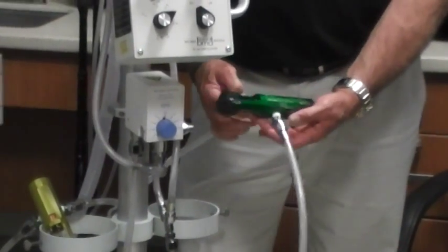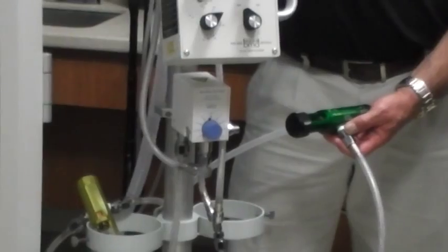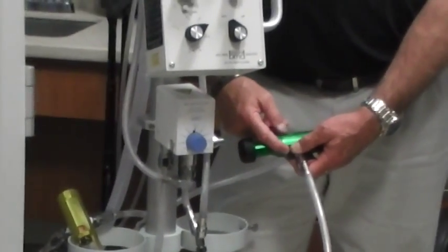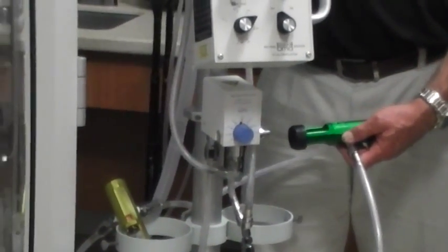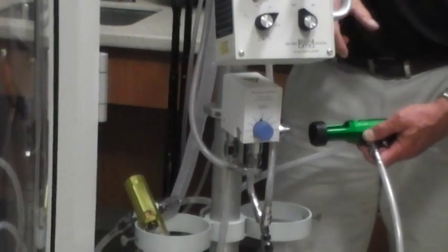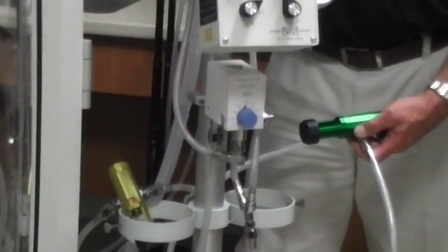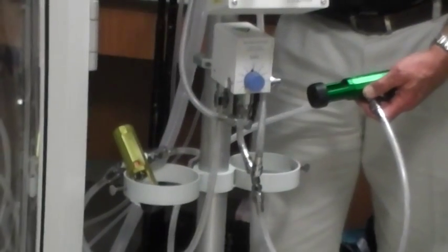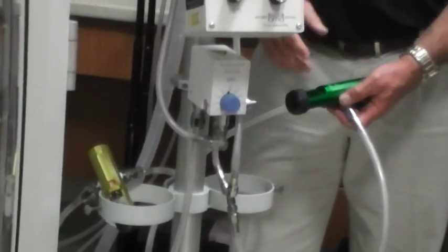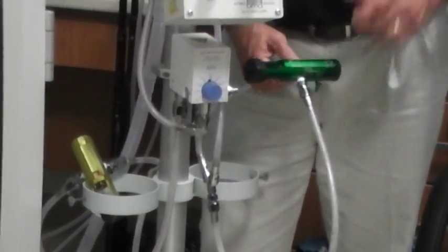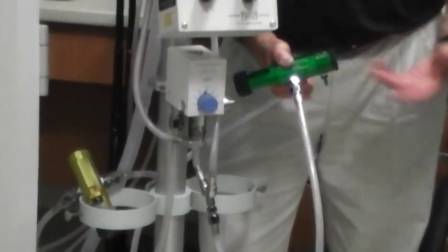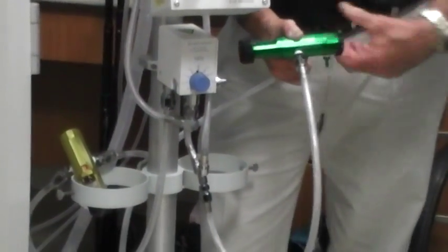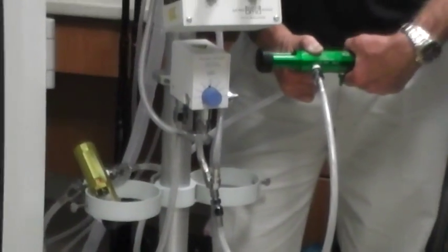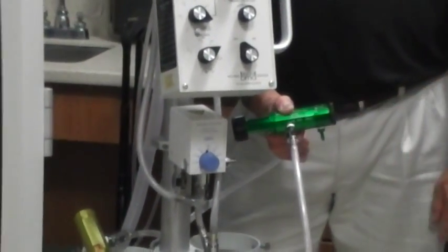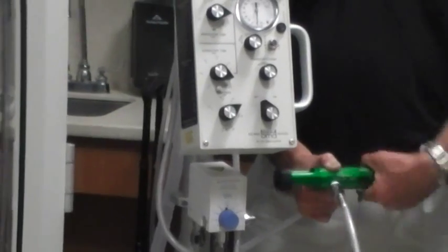The other really nice thing is you can be connected to the wall and the tank at the same time. So when you need to transport, you just make sure your tanks are on and disconnect from the wall, and then plug back in, so you don't get any blender alarms. It's just a seamless transition. If you become extubated and you need flow for your resuscitation bag, you can use that there.